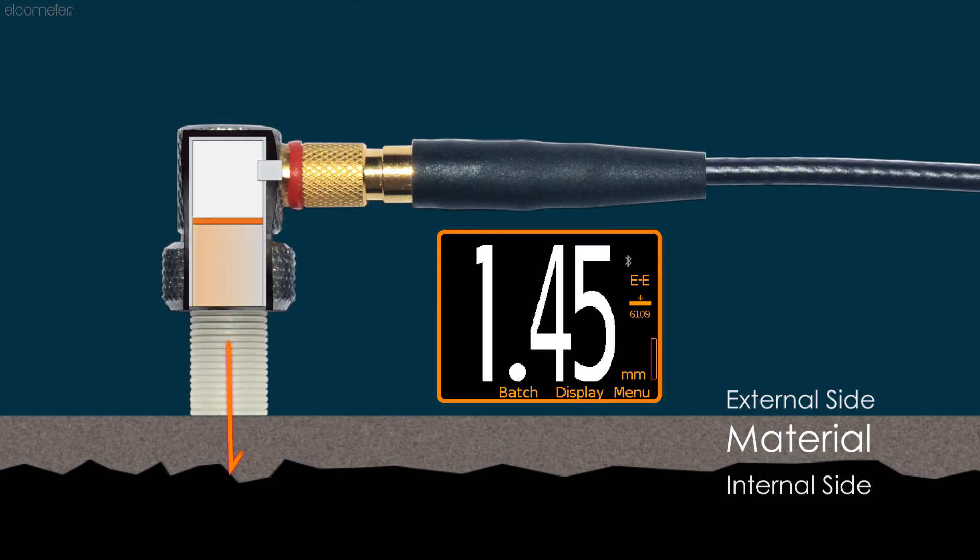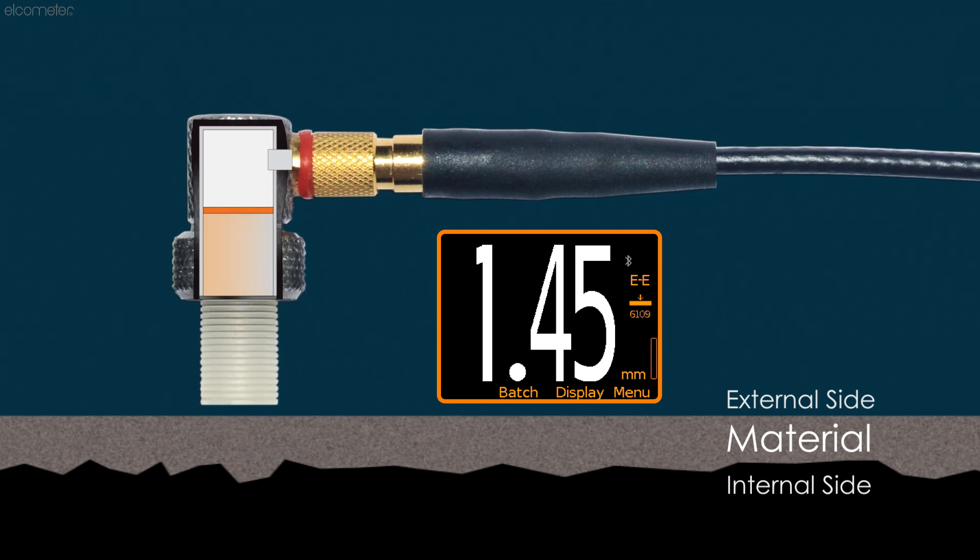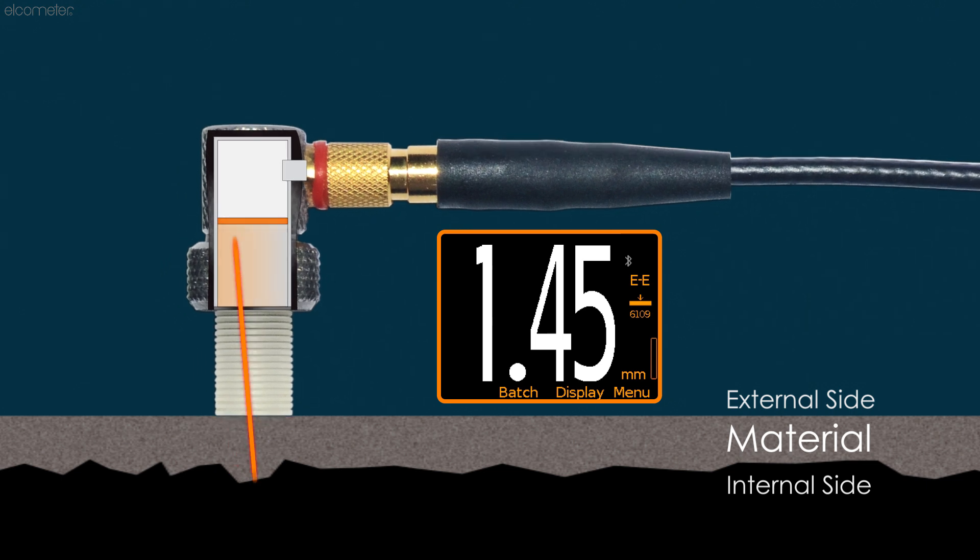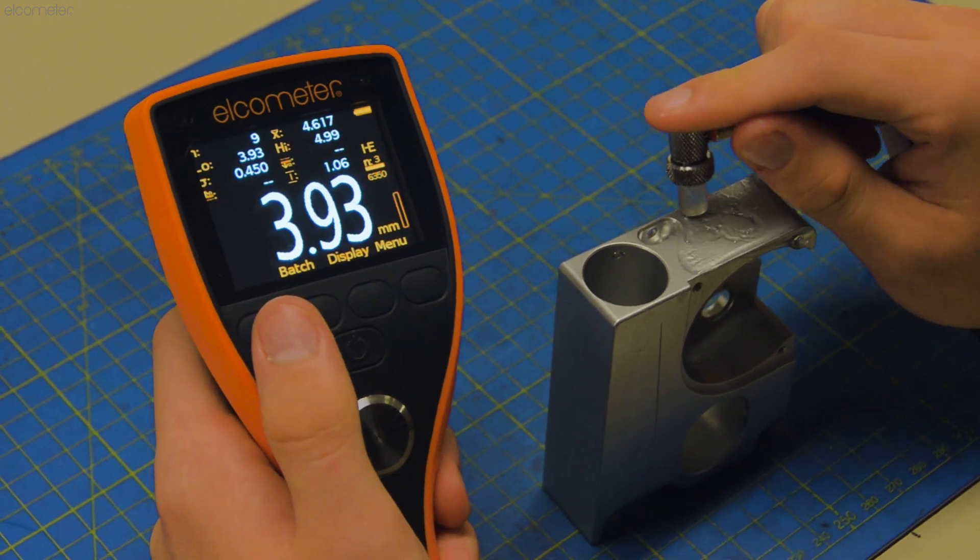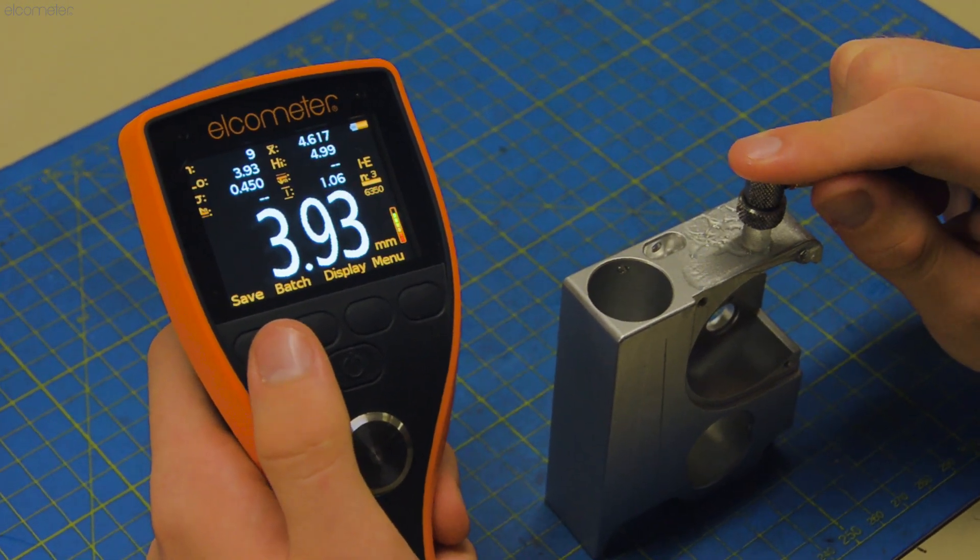When measuring on materials that deflect or absorb the ultrasonic signal, the Elcometer PTG gauges only allow you to save a measurement if the signal strength indicator is in the green, avoiding false or incorrect readings.